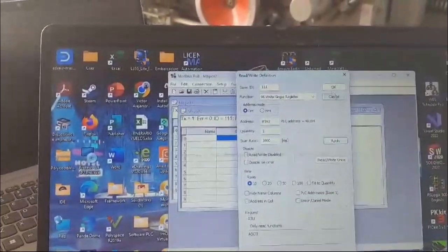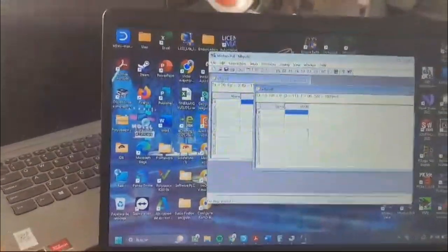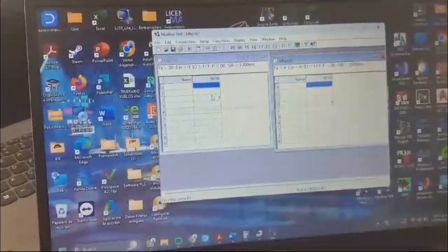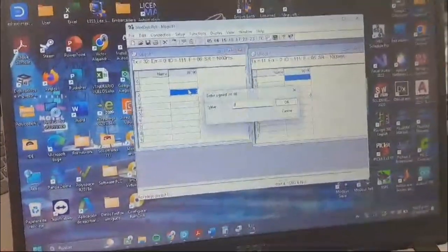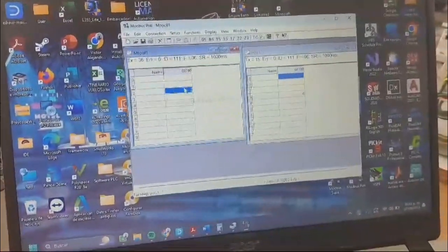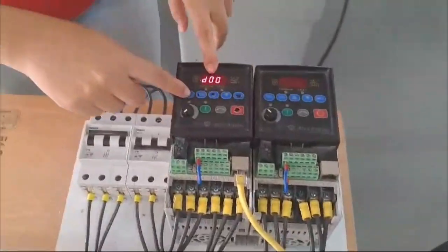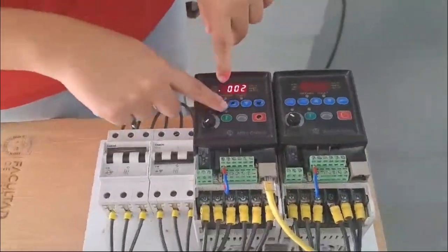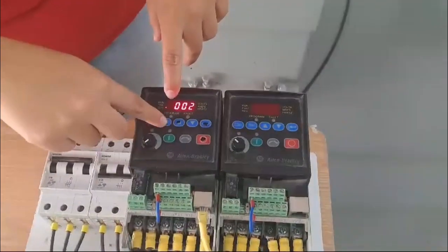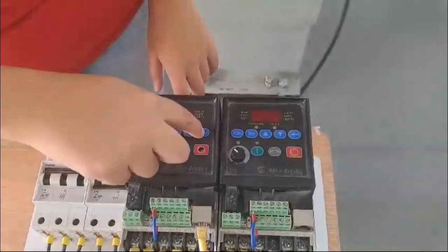In the first tab, we'll send a value of 1 and 2 to stop and start the VFD, and in the second tab, we will send a value in decimal of the desired frequency between 0 and 200. This comes from the 16-bit concatenation of the 8192 address. Now we move to the configuration of the registers A103, A104, A107, P036 and P038.